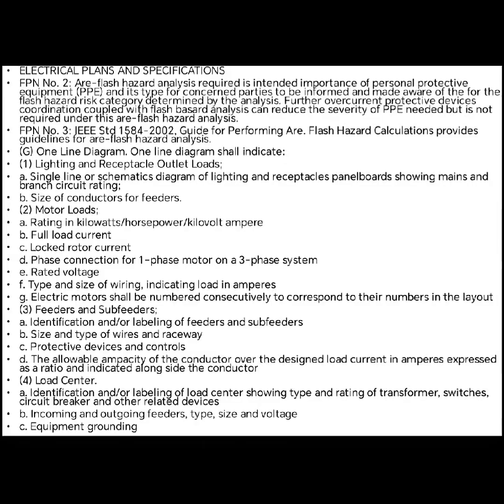distribution system: mains, panels, circuits. It must include specific details like lighting and receptacle loads, a separate line for each type of load, motor loads, size of conductors, full load current, locked rotor current, etc. Phase connections: how a single-phase motor connects to a three-phase system. Wiring: type, size, and ampacity of conductors. Feeders and sub-feeders: identification, labeling, and sizing. Protective devices: ampacity and settings. Load center, transformer, and switch ratings, incoming and outgoing feeders, and grounding. In short, the document sets the standards in creating electrical plans that ensure safety, arc flash analysis, and proper system design, with one-line diagrams with detailed load and equipment information.